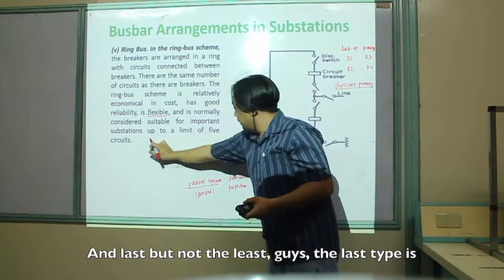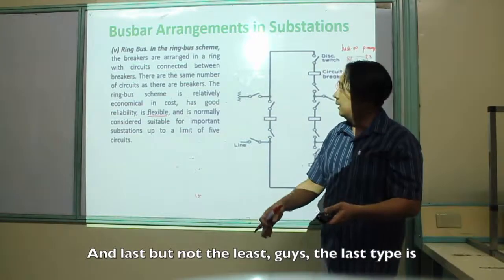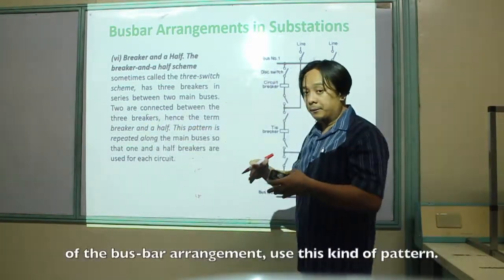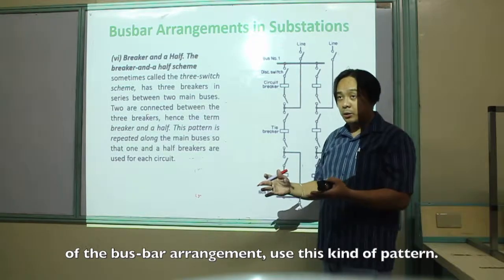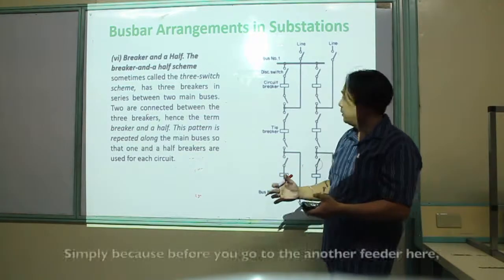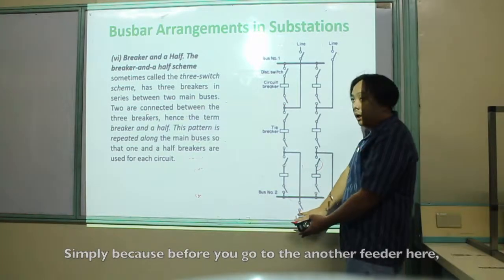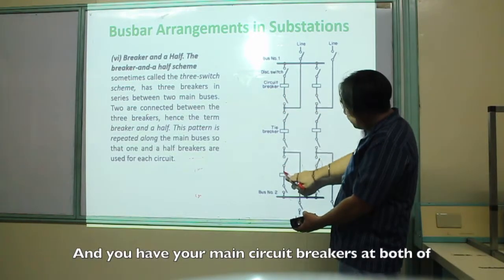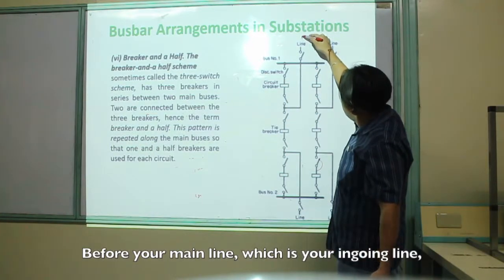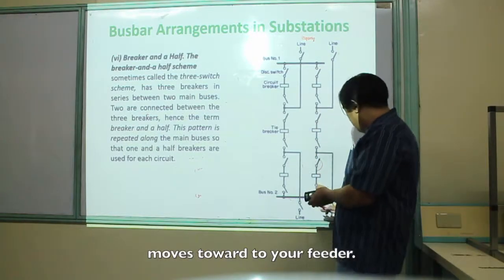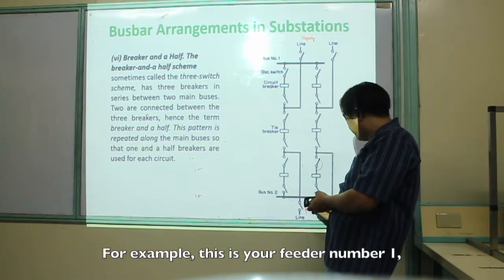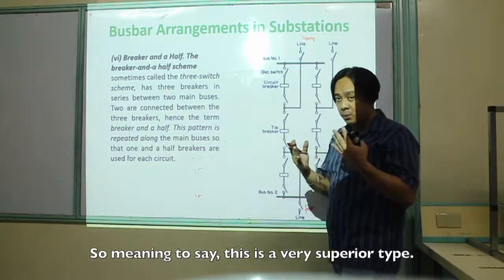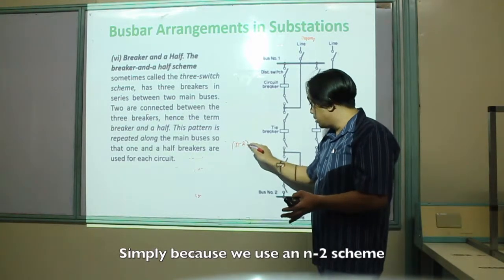Last but not least is the breaker-and-a-half arrangement. This is very familiar because the majority of bus bar arrangements use this pattern. It is called breaker-and-a-half because before moving to another feeder, it is separated by one and a half breakers. You have a tie breaker and main circuit breakers at both bus bars. Before the incoming line moves toward the feeder, it passes through one and a half breakers. This is a very superior type simply because it uses an N-2 scheme.